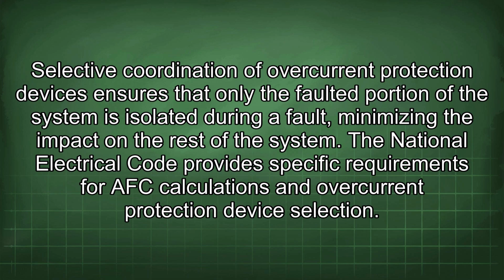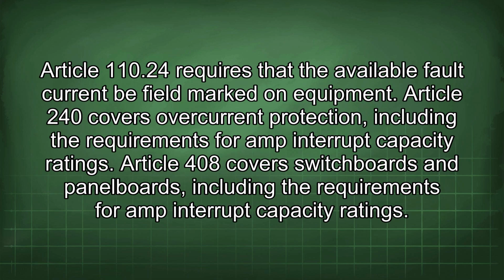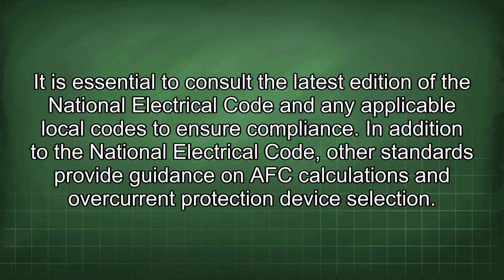The National Electrical Code provides specific requirements for AFC calculations and overcurrent protection device selection. Article 110.24 requires that the available fault current be field marked on equipment. Article 240 covers overcurrent protection, including the requirements for amp interrupt capacity ratings. Article 408 covers switchboards and panel boards, including the requirements for amp interrupt capacity ratings. It is essential to consult the latest edition of the National Electrical Code and any applicable local codes to ensure compliance.